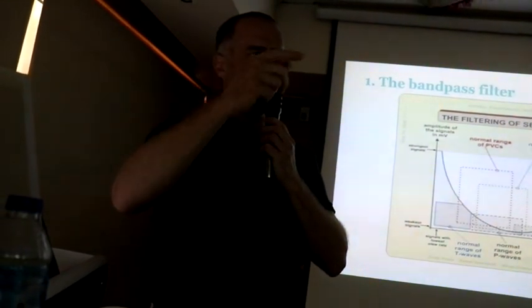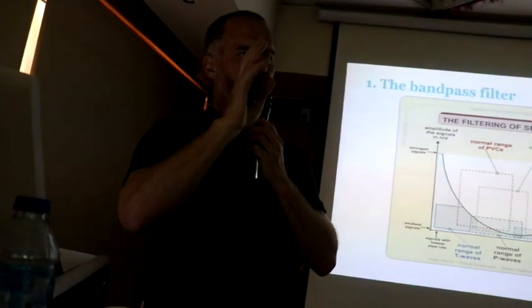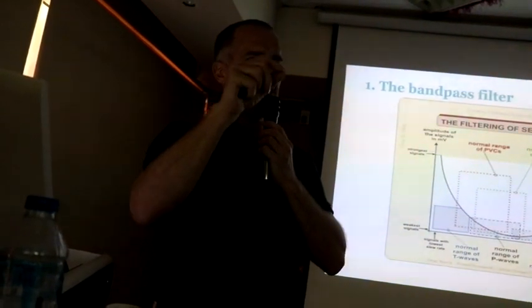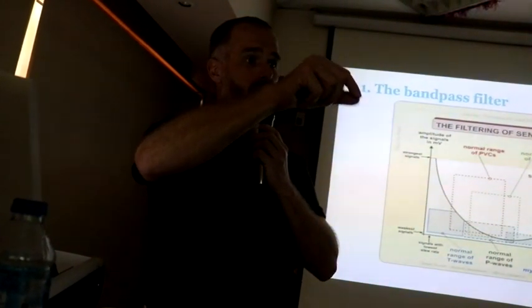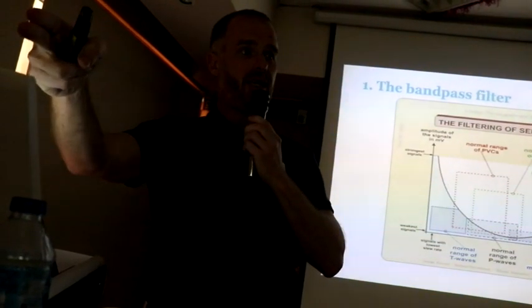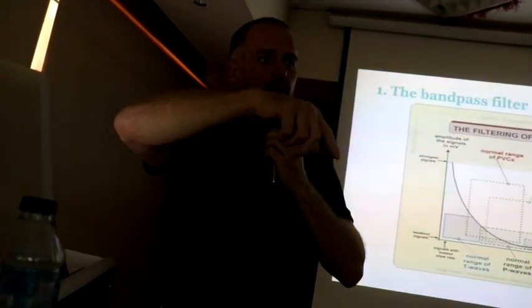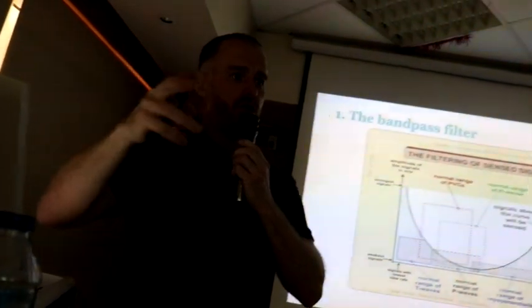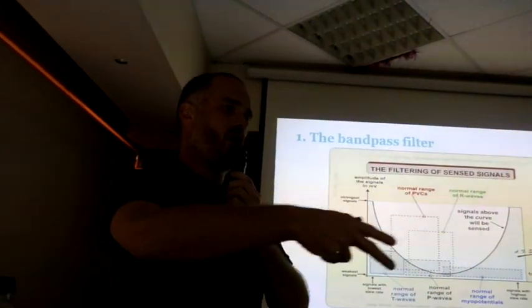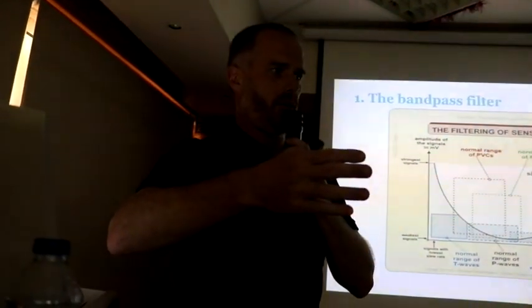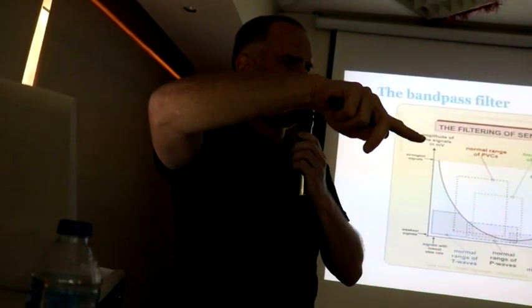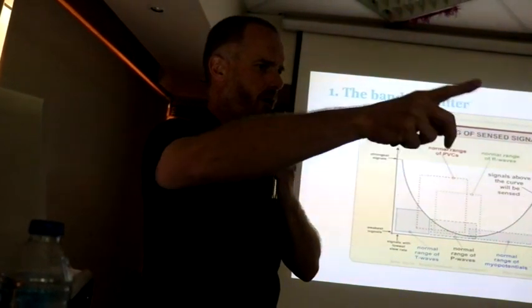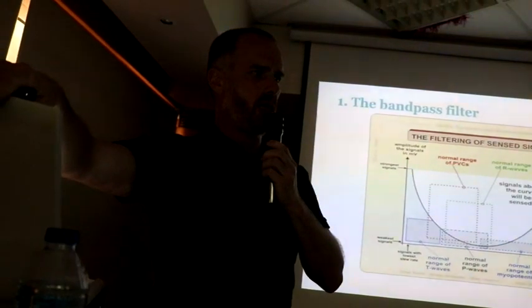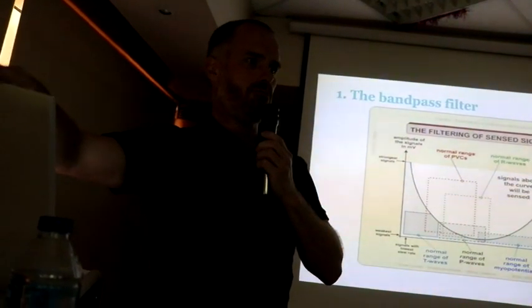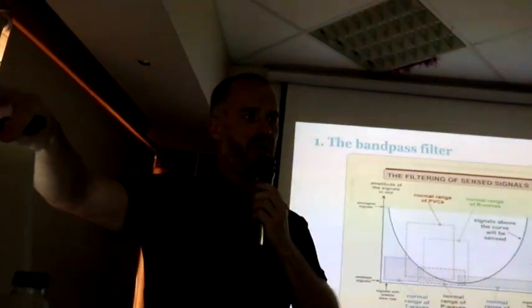Typically, you could try this next time. Usually, if you measure the signal on a Medtronic PSA, it will be smaller than our signals. So with Medtronic maybe you get 6, with Abbott you might get 8. But can you imagine if it's 4, right? If it's 4 on a Medtronic PSA, you might move the lead, right? It might be 6. So we would recommend you use our PSA filter on the pacemaker that you're going to put in.